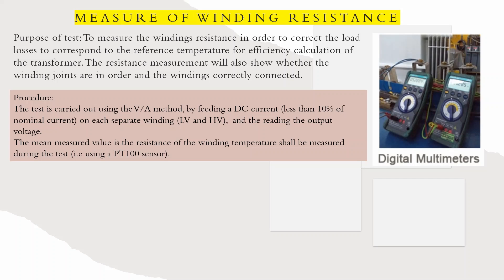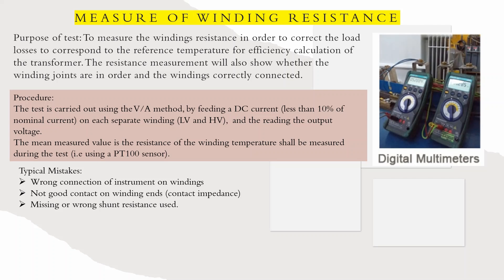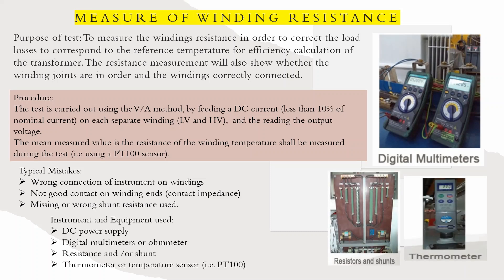The windings tested are LV (low voltage) and HV (high voltage), reading the output voltage. The main measured value is the resistance of the winding; temperature shall be measured during the test using a PT100 sensor. Typical mistakes include wrong connection of instrument, winding not having good contact at winding ends, and missing or wrong shunt resistance. Instruments used: DC power supply, digital multimeter or ohmmeter, shunt, thermometer, and temperature sensor.